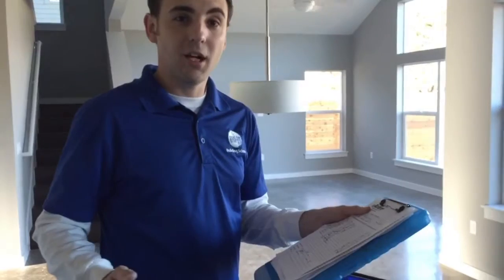So all controls are different. There are different ways to achieve max airflow. Sometimes you just have to turn on the fan to high speed. Other times it's important to have it in max cooling in order to get the amount of airflow out of the ducts that you want. Typically, the HVAC contractor leaves me a copy of their test and balance report. This report shows the designed airflows and the numbers that they actually got, and it shows them testing and balancing the equipment in accordance with the Manual J design airflows. So now all I have to do is check their work and make sure that the right amount of airflow is coming out of each duct.